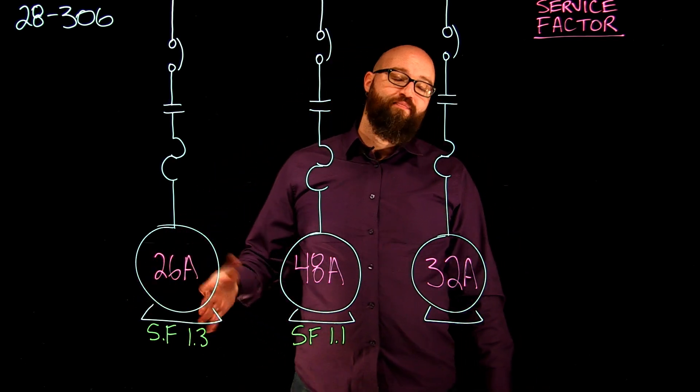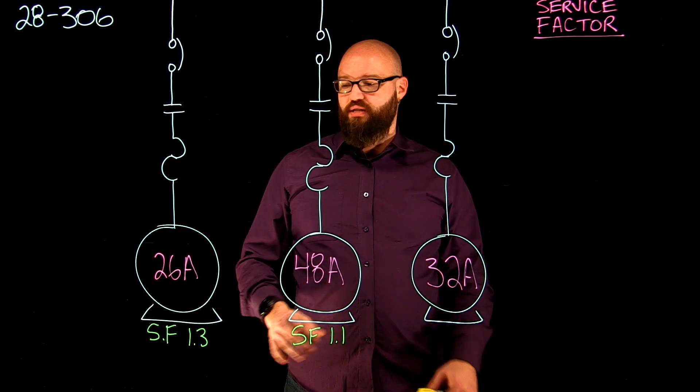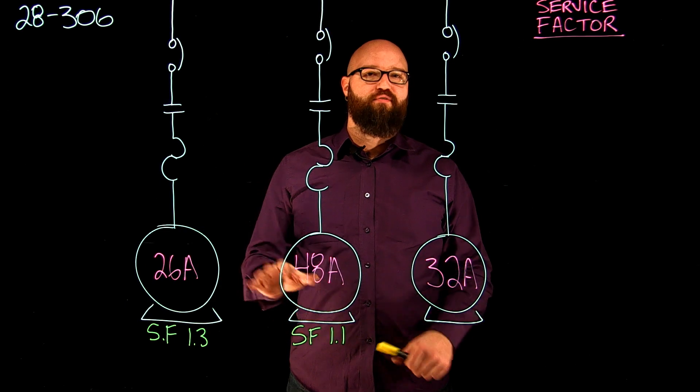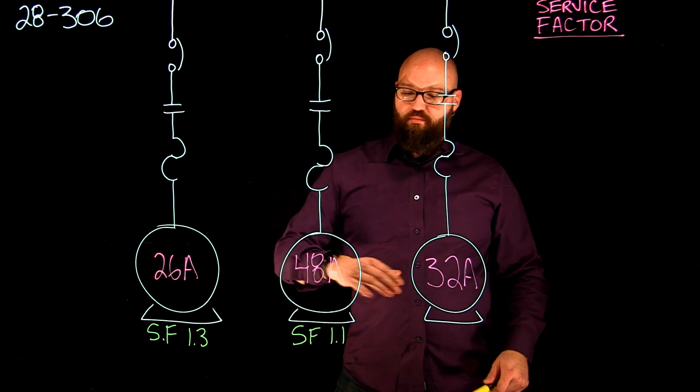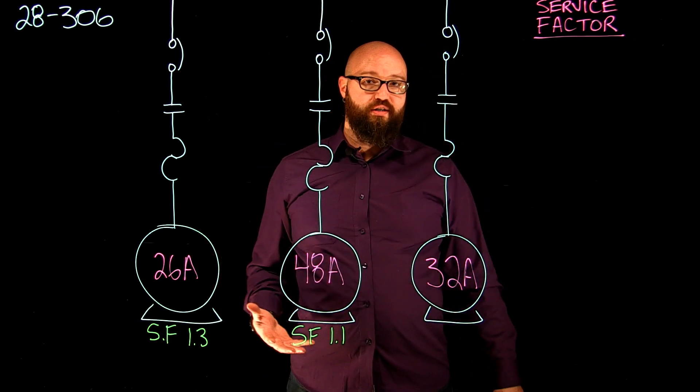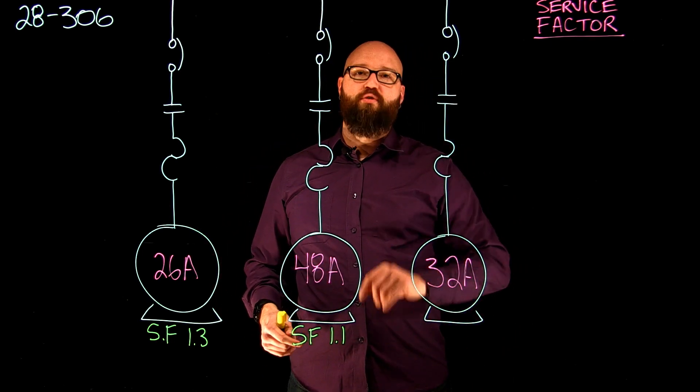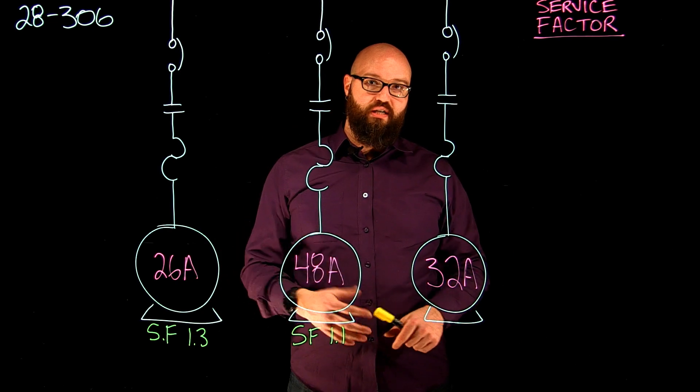For example, with this first motor we have a service factor of 1.3, which is 130%, so it can run about 130% for short durations without causing major damage to the motor windings. Our second motor is 1.1 or about 110%, and then our third motor here is not marked, and we'll discuss that in a minute.